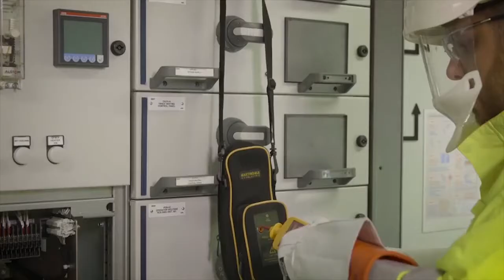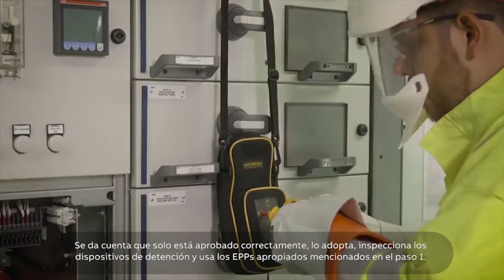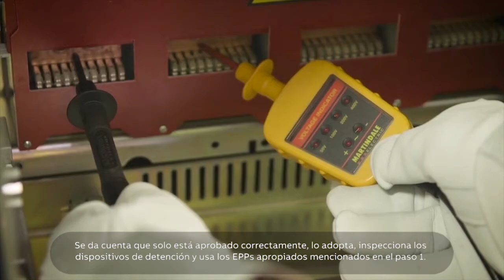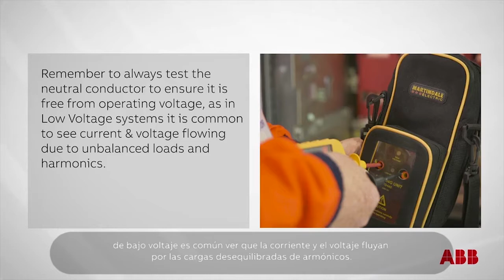Step 4. Verify the absence of operating voltage. Utilize only approved, correctly rated and inspected detection devices and wear the appropriate PPE identified in Step 1. Remember to always test the neutral conductor to ensure it is free from operating voltage, as in low voltage systems it is common to see current and voltage flowing due to unbalanced loads and harmonics.